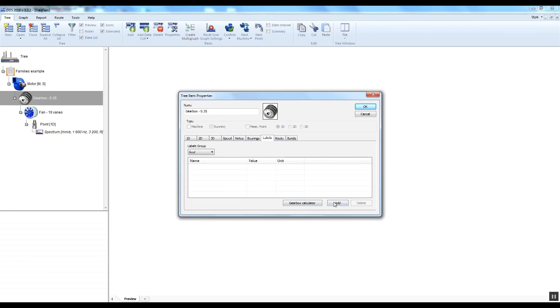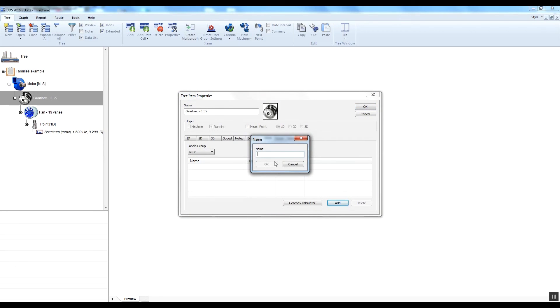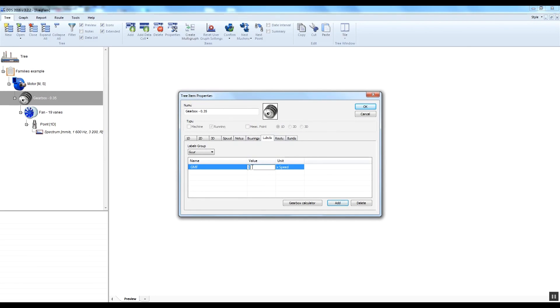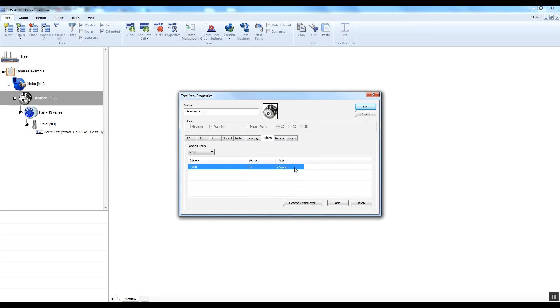I press Add and enter GMF as the name of the label. Now I enter 13 and then I select multiplying by the speed item. In this column you can select multiplication by speed, hertz, RPM, CPS, or CPM, but we need multiplied by speed.